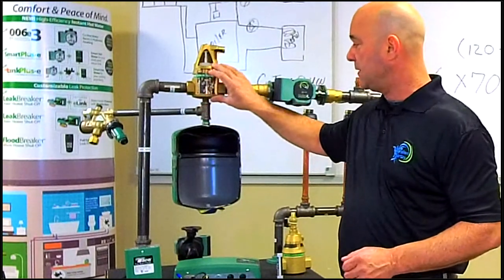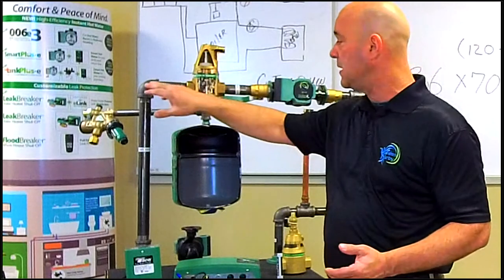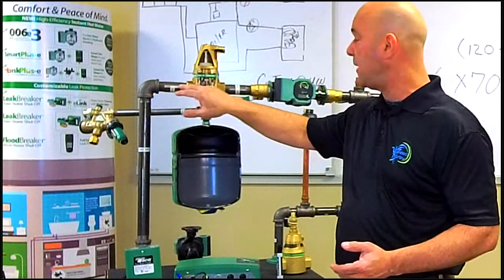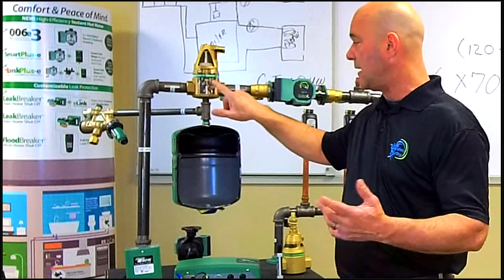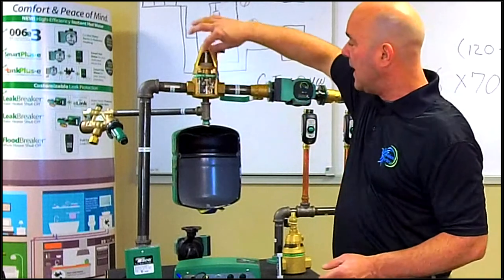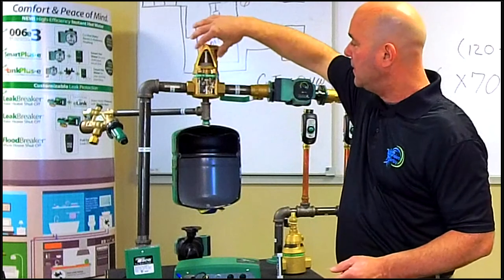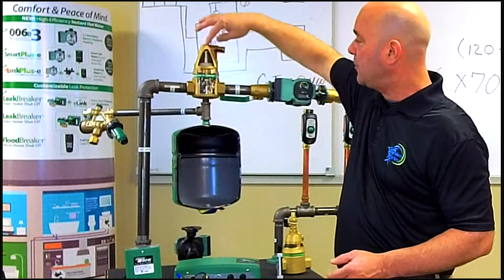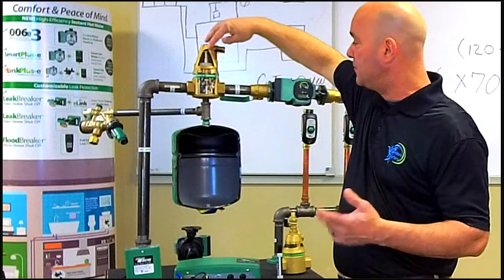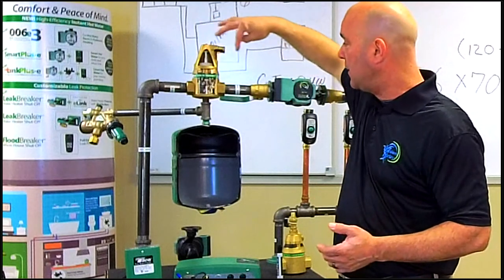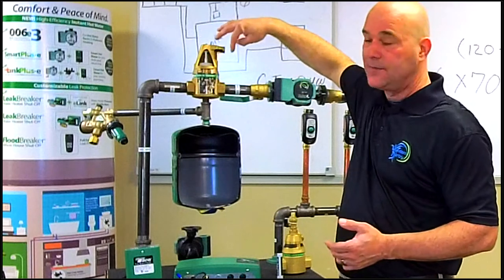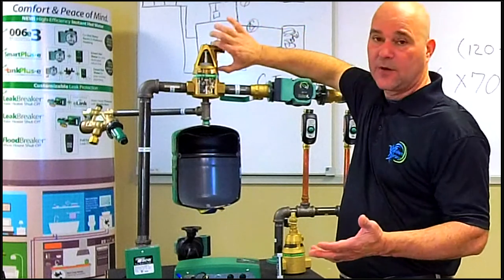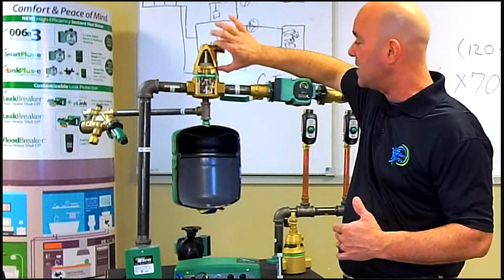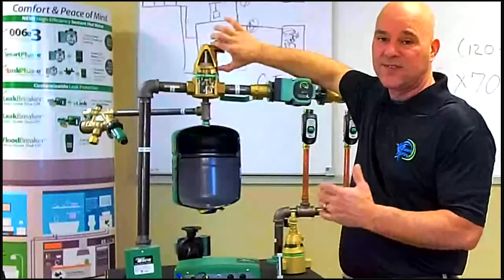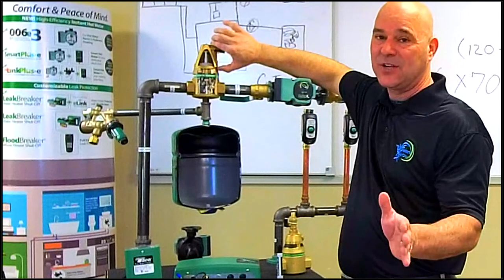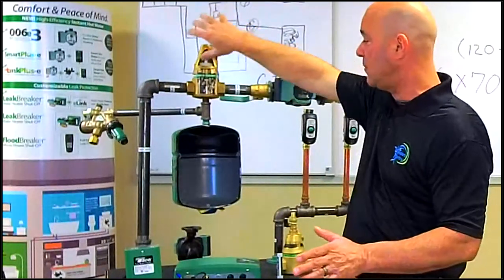So what is the responsibility of this air separator? The responsibility is to take any air that may be flowing through this pipe, run through these Pall rings. This is a Taco 4900. Take the air, bring it up to the top of this chamber, this taper on the chamber. We never put water all the way up to the top, so these are very robust. We bring the air up and we expel the air out of the 4900. Just to let you know, this is a commercial product. We brought it down into the residential market. This upper portion of the 4900, we use that same device all the way up through our 8-inch air separators, just so you understand how robust that is.